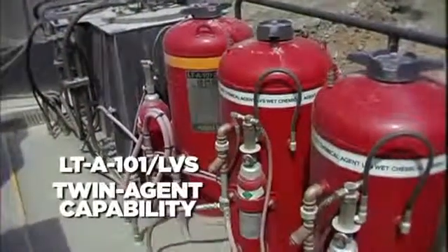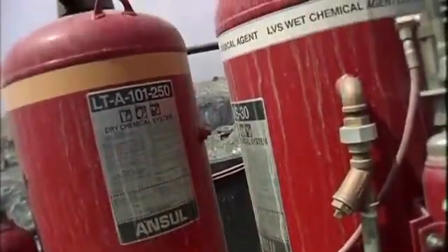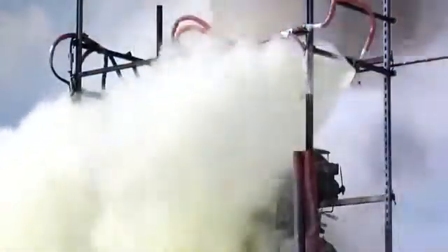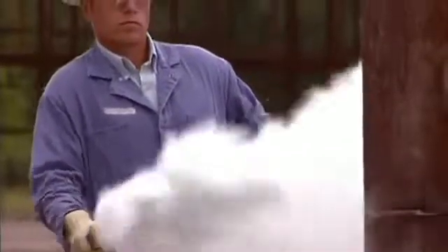An outstanding stand-alone system in and of itself, the versatile Ansul LVS product can also be used in a twin agent configuration employing the Ansul A101 dry chemical system. When used as part of a twin agent system, the dry chemical portion acts to quickly knock down flames, while the LVS liquid agent cools and blankets adjacent surfaces. Both dry and liquid systems are designed for simultaneous discharge when actuated either manually or automatically.